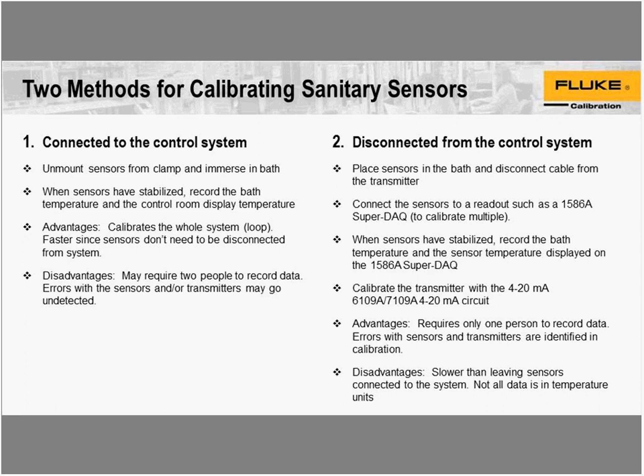I'm not sure if it's mentioned anywhere in the slides, but something that was pointed out to me with the tri-clamp bath is that if you are calibrating a transmitter, you can configure a transmitter to display units. We'll talk about that a little bit more when we get to the transmitter section at the end. But you can quickly put in a configuration that converts a 4 to 20 milliamp signal to the unit you want to measure it in, which in this case would be temperature.